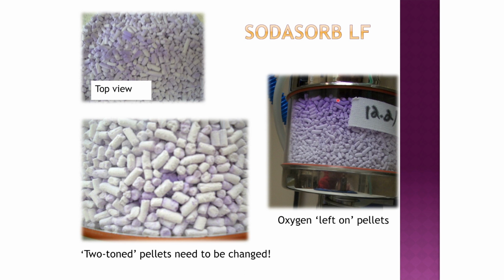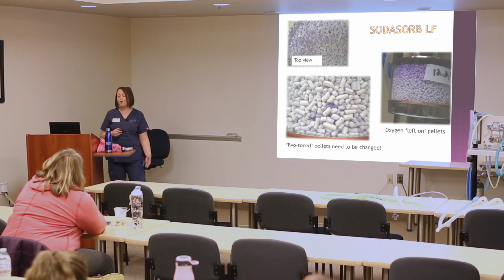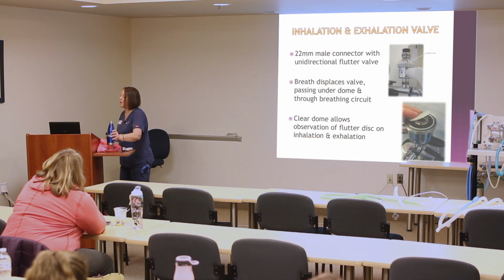So this indicates the pellets are a little bit desiccated, but I don't always change it when that happens because it's not exhausted. So this is how I know when you guys leave the oxygen on. And now you will know too. You'll be able to look in and see purple on the top, somebody left the oxygen on, or there's a problem with that needle valve.